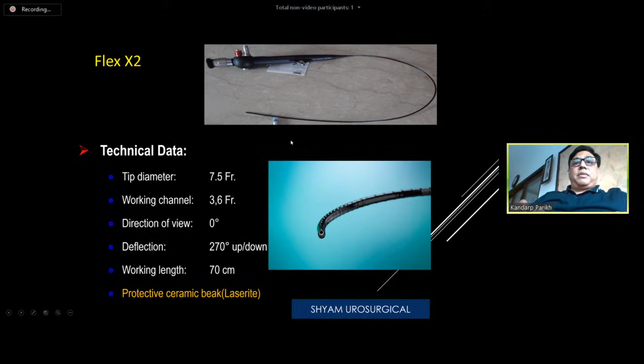Now, if you look at the tip of the scope, these are the two scopes. One is from Olympus, where they have got a bullet tip. The diameter here at the extreme end is 4.95 French. Otherwise, the tip diameter is 7.5 French. Similarly, in case of Storz, it is 7.5 French. In Storz, they have got this whitish structure, which is known at the tip of the accessory channel. This opening is for the accessory channel. So here there is a ceramic beak, the white color ceramic beak, which protects the accessory channel from possible laser injury. If you misfire the laser, it will prevent the injury to this. This is a patented technology from Karl Storz.